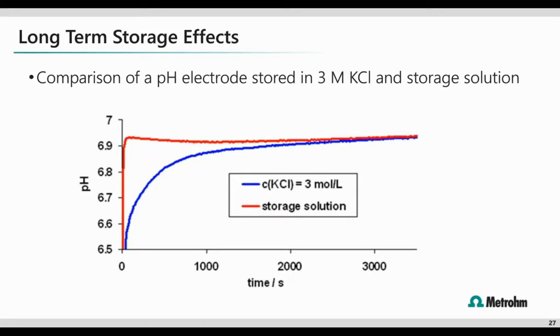The red line represents the measurement taken from an electrode that was stored in the buffered electrode storage solution. So you see the pH measurement response is very quick and it's very stable. So really the take-home message here is keep your electrode in storage solution, especially for those overnight storages, and you'll be immediately ready to make measurements the next day.